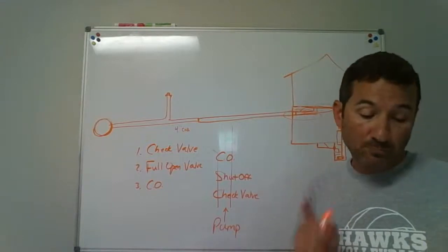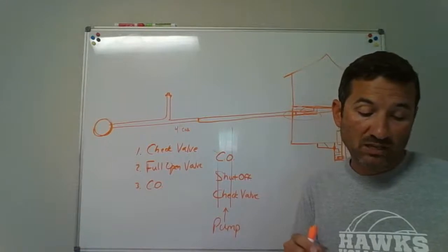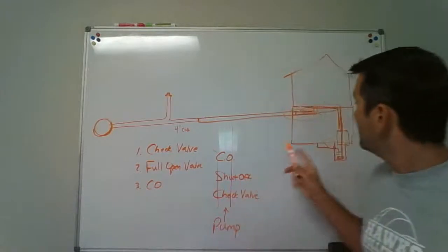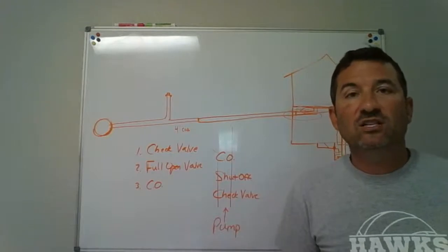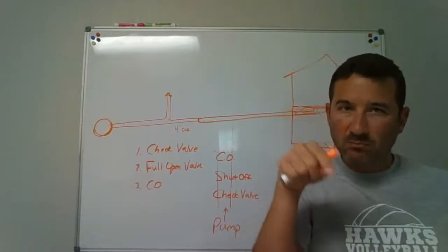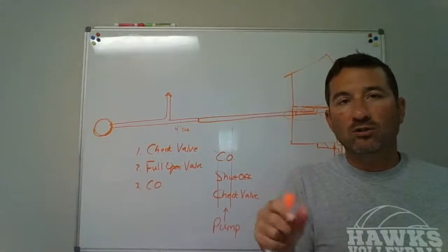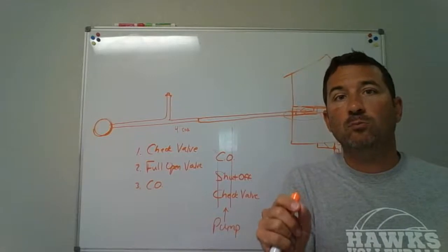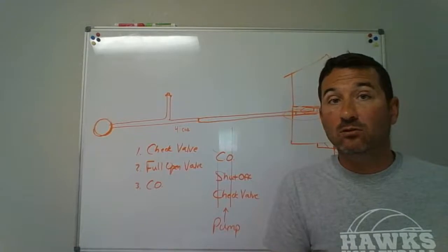Okay, the discharge pipe and fittings. Discharge pipe and fittings serving the sump pumps and ejectors shall be constructed of materials pressure rated. So that PVC we've been putting in for all our drainage stuff is called foam core. It's a hard shell on the inside, a foam in the middle of that core, and then a hard shell PVC on the other. It's not solid PVC. So ours is stamped right on the side. It says not for pressure. That's cellular core, foam core PVC. If you get the solid PVC, it's pressure rated pipe.